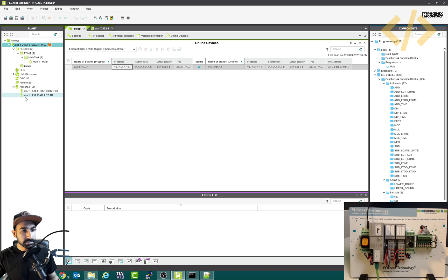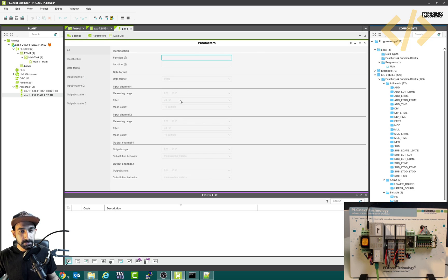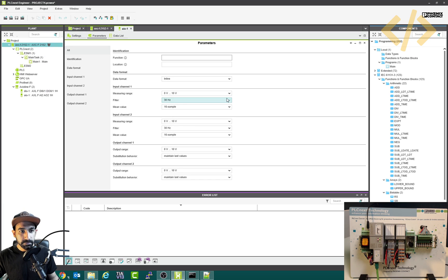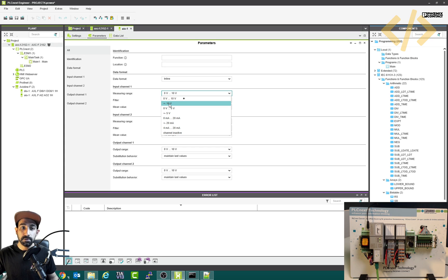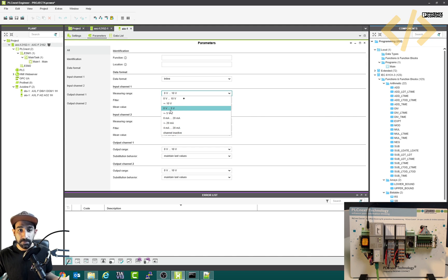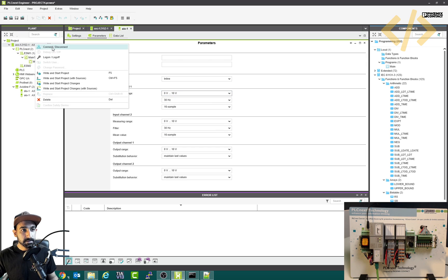If you open this analog IO here in X09 and open the properties, go to parameters — it's faded because we are online. You can see input channel one is set to zero to ten volts, showing the frequency of reading and the resolution. You can change this to plus-minus ten volts, zero to five volts, plus-minus five volts, or current range, depending on your analog input. You can also make it inactive.